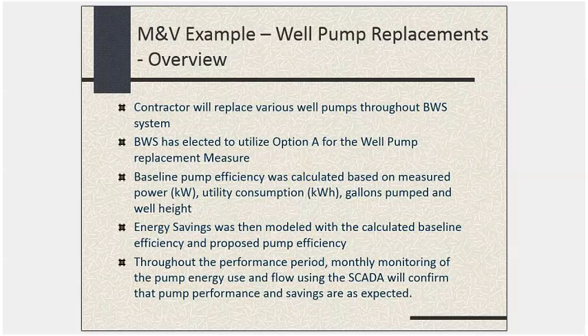Now we're going to touch on a few examples of ECMs here as M&V examples at your specific project. You decided on using option A for the well pump replacement measure, and the baseline pump efficiency was calculated based on measured power, utility consumption, gallons pumped, and well height. So you're focusing on key variables that determine a lot of the future operation and consumption profile of that pump equipment, giving a good picture of what was occurring during the baseline period. Then you're modeling the energy savings with calculated baseline efficiency and a proposed new pump efficiency.